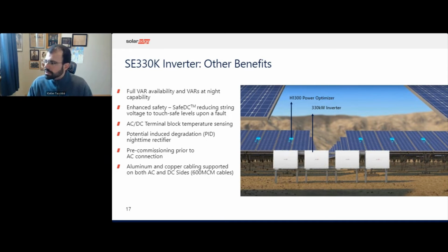It brings down the voltage for each optimizer, the output of each optimizer, to 1 volt within 3 to 5 minutes, okay? The AC and DC terminal blocks include temperature sensors indicating if connections become loose or need checking. PID mitigation system is included as standard for this inverter, and pre-commissioning of the system is possible as long as the DC array is connected, okay? We heard we have this in the Synergy platform. We heard that was bringing benefits to the customers. We kept it in this platform to allow the inverter system to be commissioned prior to AC being available, speeding up plant connection.